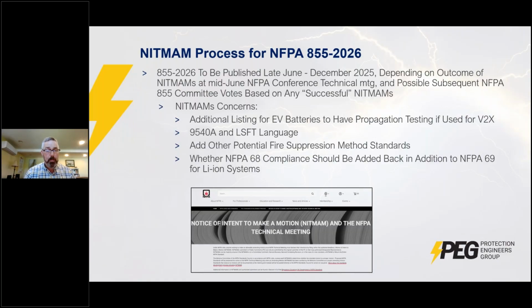if this thing does fully evolve in a fire, what's the damage? How much fire comes out? How big is the fire, and so forth? They quantify it. So there's a new push for large-scale fire testing. That's something some of the AHJs have been asking for outside of the standards development cycle, and now the standard is trying to step up and put something in place to deliver that. UL is looking at updating 9540A to address that. There's a 9540B, I think, that does that for residential, and CSA has a standard that's written a process to do it as well. CSA 800, that's an option that could be considered.